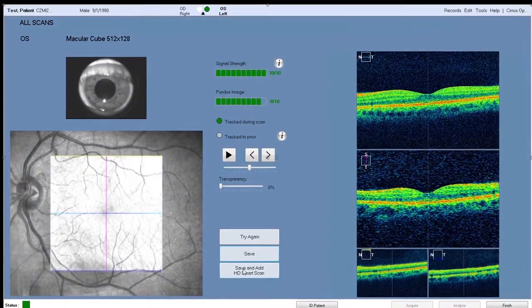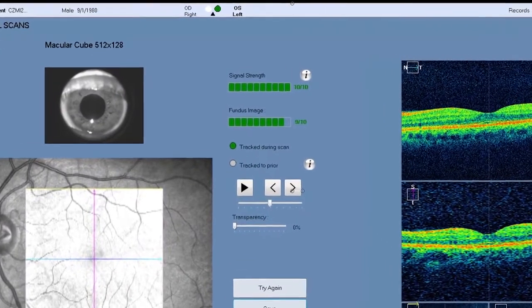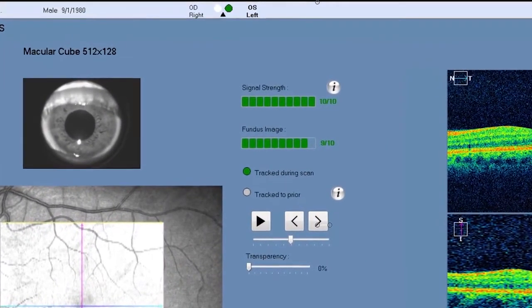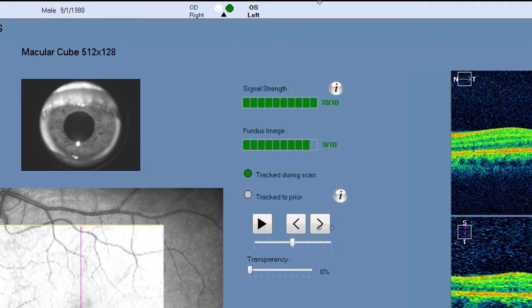For the best OCT image, the goal is to get the highest signal strength. The signal strength indicator is located in the center of the review screen after acquiring an image and applies to the scan overall. The best images are obtained when the signal strength is a score of 8 or better.